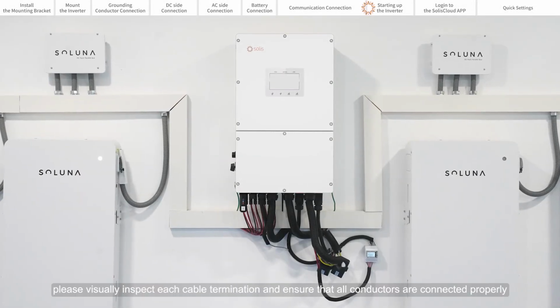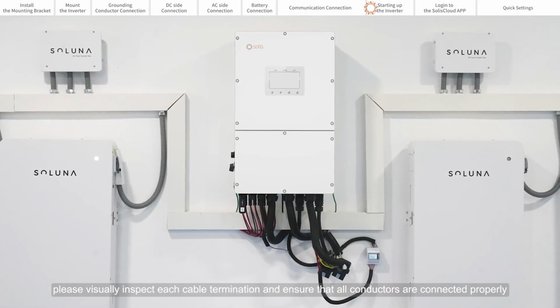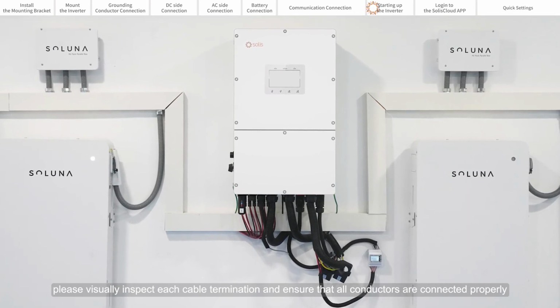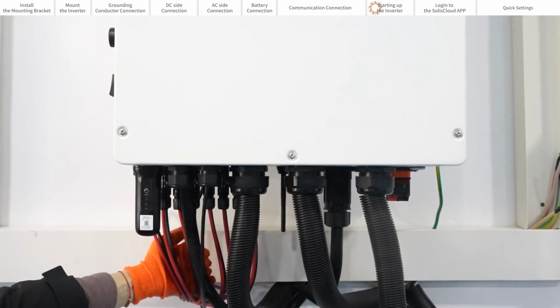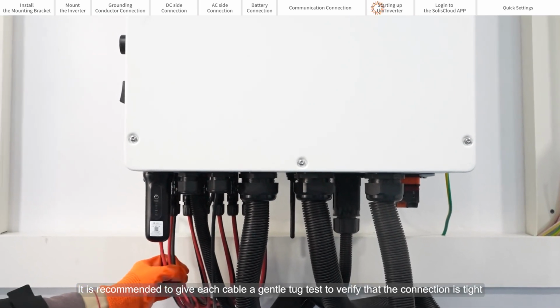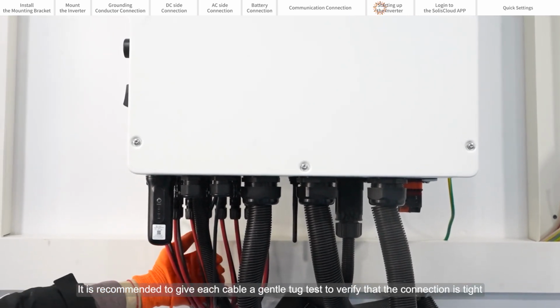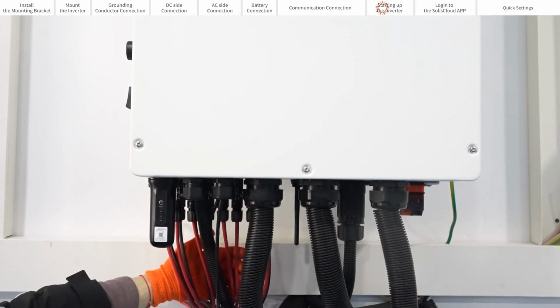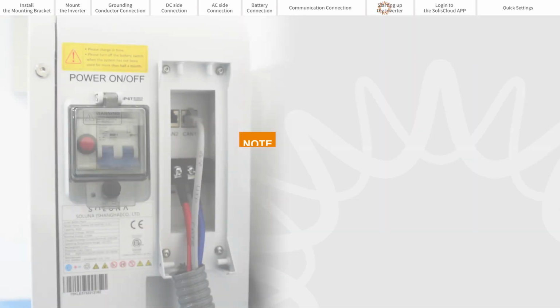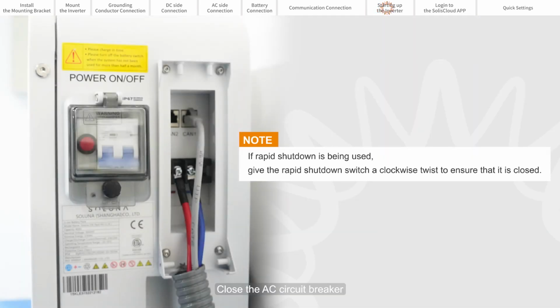Starting up the inverter. First, please visually inspect each cable termination and ensure that all conductors are connected properly. It is recommended to give each cable a gentle tug test to verify that the connection is tight. Close the AC circuit breaker. Turn on the battery.